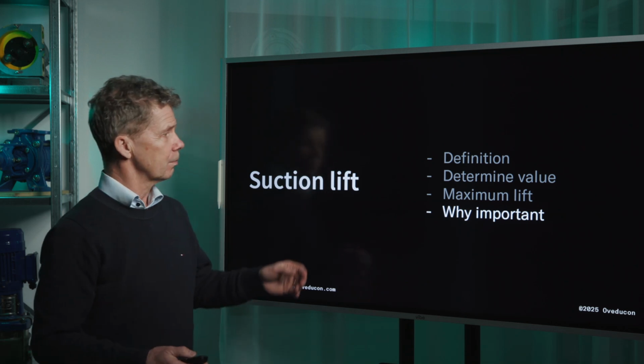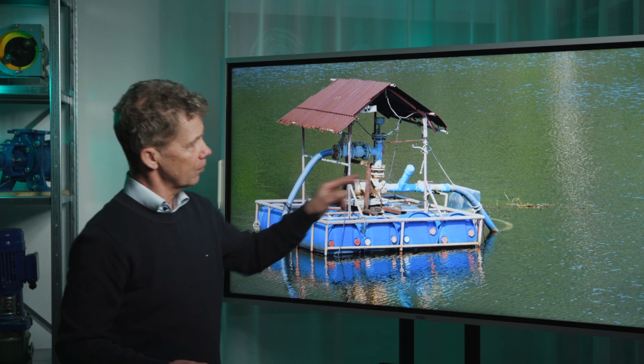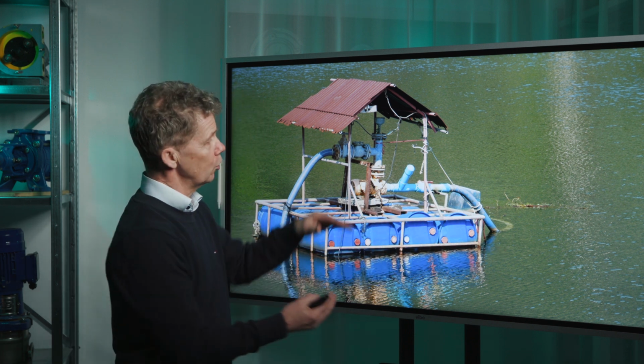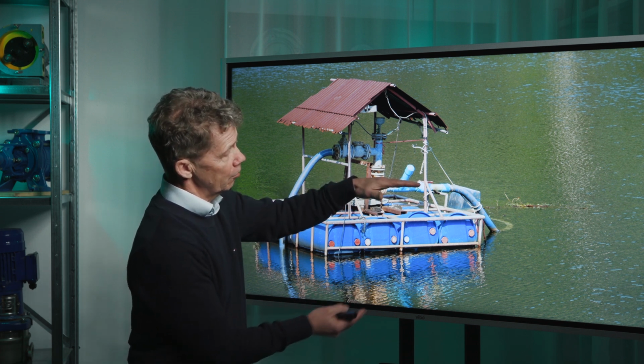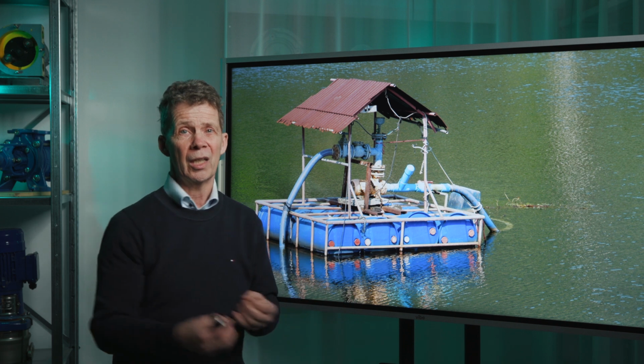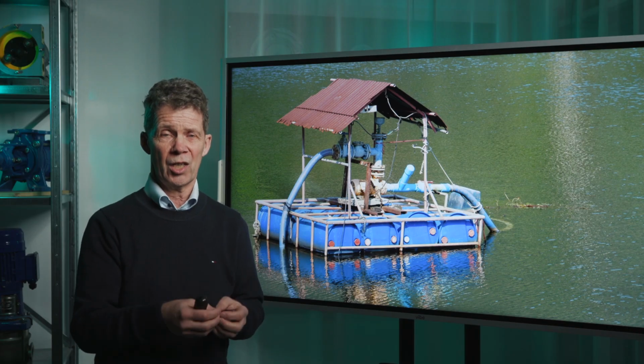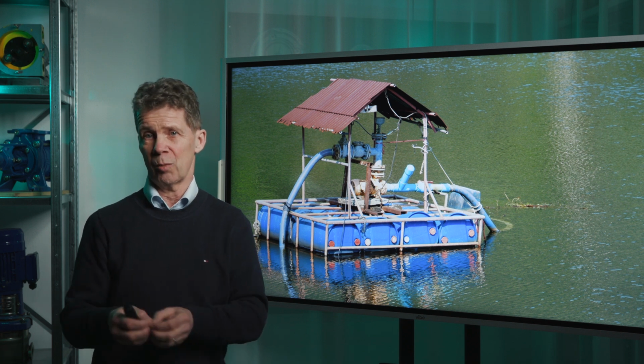I already told you something about the suction lift, but why is it important to know the value of your suction lift? I will tell you. In this case we have a pump here, a suction line and a medium level, and to determine the suction lift you can measure the distance from the eye of the impeller and the medium level, and then you have a precise value. And you need that precise value of the suction lift in your NPSH calculation to avoid damaging cavitation. So work with precise data and not with rough estimate data.